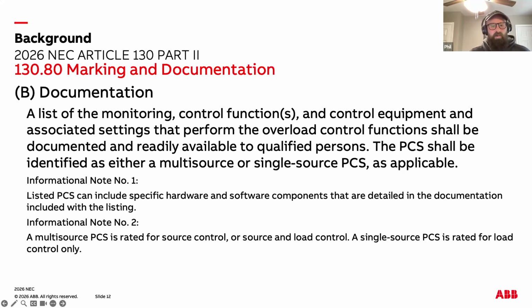That does mean that in order for an inspector to properly verify safe operation and successful installation of a PCS, they will have to actually look at the commissioned software. I know that is anathema to most electrical inspectors. Sorry if there's any on the call, but it is part of the evolving code that inspectors will have to actually look at a screen to see if the settings are input correctly.